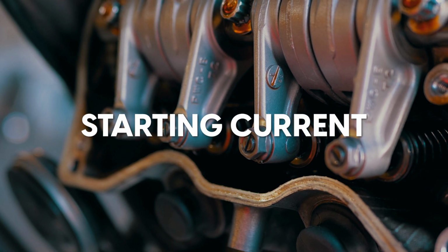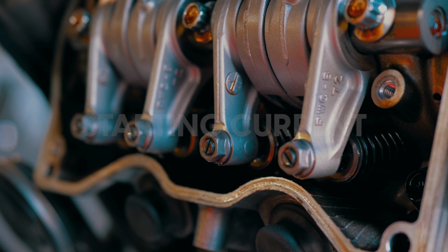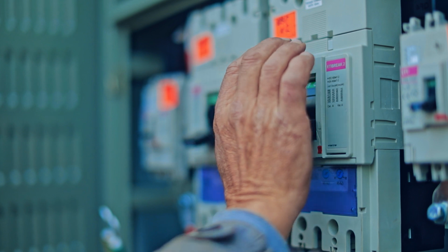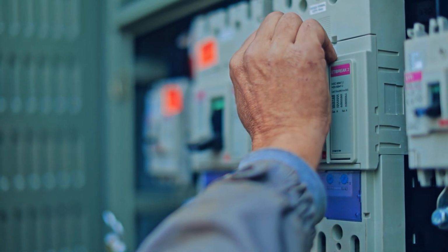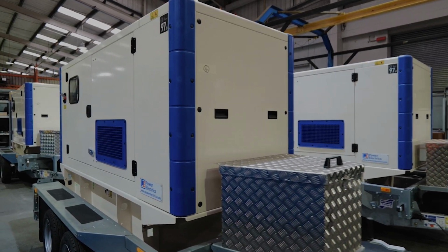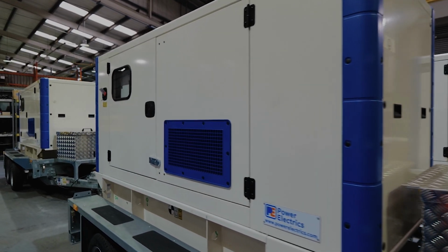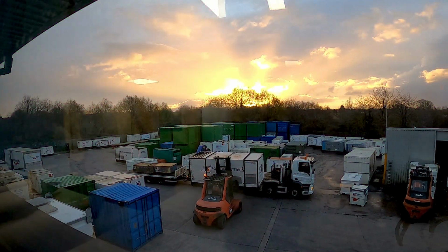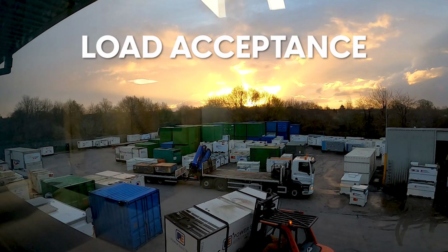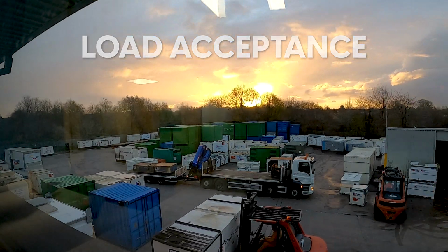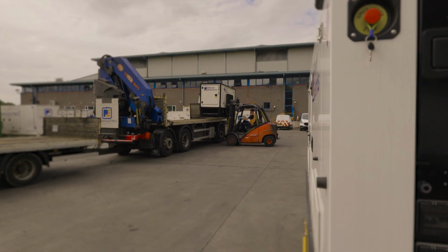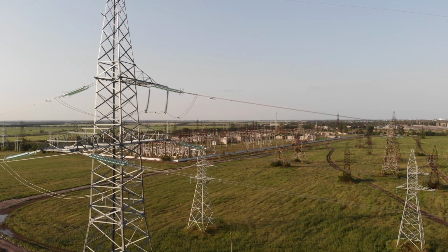Starting current, also referred to as switch-on surge, is the high current flow, typically experienced by a motor or similar during the first few moments of switching on. Load acceptance is the maximum load, in percentage, that can be applied whilst maintaining performance classes.